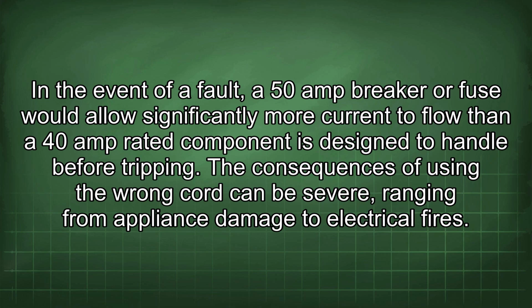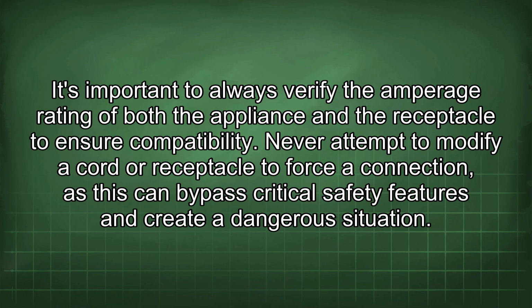In the event of a fault, a 50 amp breaker or fuse would allow significantly more current to flow than a 40 amp rated component is designed to handle before tripping. The consequences of using the wrong cord can be severe, ranging from appliance damage to electrical fires. It's important to always verify the amperage rating of both the appliance and the receptacle to ensure compatibility.